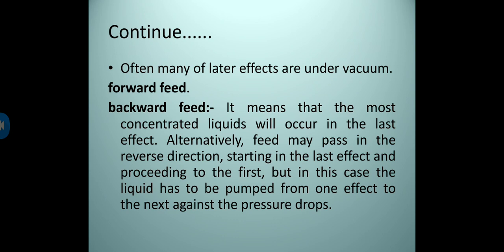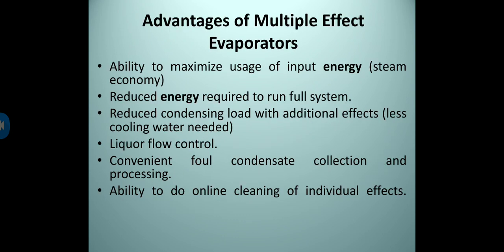In backward feed, the most concentrated liquid will occur in the last effect. Alternatively, feed may pass in the reverse direction, starting in the last effect and proceeding toward the first, but in this case the liquid has to be pumped from one effect to the next against the pressure drop. That is the backward feed.